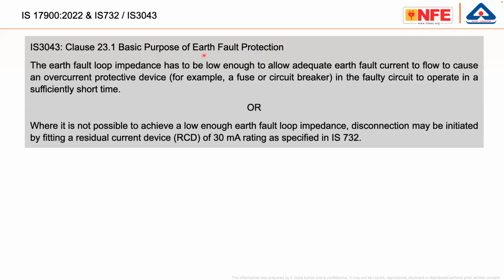So fault protection is what is shown here. In IS 3043, since 1966, the concept which is followed is, you can read here, the earth fault loop impedance has to be low enough to allow adequate earth fault current flow to cause an overcurrent protective device, for example, a fuse or a circuit breaker in the faulty circuit, to operate in a sufficiently short time. So that means the first paragraph says the fault loop impedance of the circuit has to be smaller so that fuses and MCBs are able to trip, or where it is not possible to achieve a low enough fault current, disconnection may be initiated by fitting a residual current device.